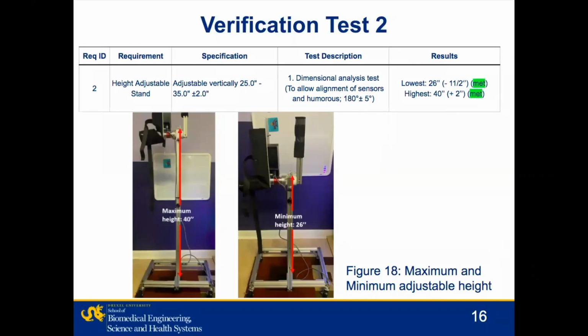For verification test 2, we verified the height adjustability of the device using dimensional analysis testing as well. And this is important to allow the alignment of the sensors to the humerus during measurement or data acquisition. So the results showed that the maximum and minimum height meet the range of the specs of the requirement. And we have that 40 inches is the max because any higher than that would cause the device to be unstable, and any lower than 25 inches, in that case, the handle would interfere with the base.